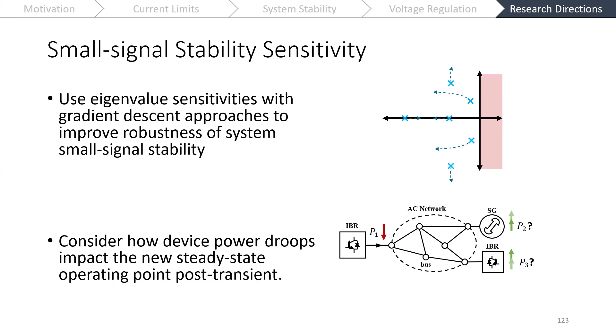Next, considering how the actual transient behavior of the power system impacts where our new steady state is going to be after a transient in the system. So, considering what the different power droops in the system are. In our approach, we just have a slack bus, which picks up extra active power when we decrease active power at a different place in the system. But in reality, lots of different devices in the system are going to be picking up that power as the frequency drops before it comes to a new steady state. And this will impact the new operating point which our devices are being linearized around.